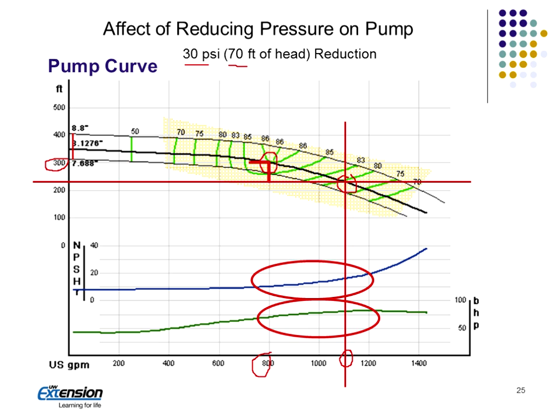So we need to make sure that the well can supply the water if we're going to allow that to happen. And there's some advantages doing this. But the other thing I wanted to show here, over here, this is a graph. This is called net positive suction head. That is the amount of water that needs to be above the pump inlet in order for it to not cavitate. So as we reduce the pressure and this flow rate increases, it actually increases the requirement for that net positive suction head. So this goes from about 10 feet of head here to probably about 18 up here. So we want to make sure we're more than 18 feet of water head when the pump is operating, so that we don't get cavitation.